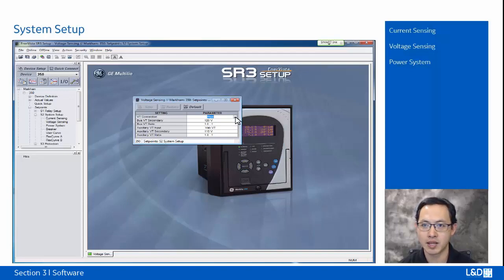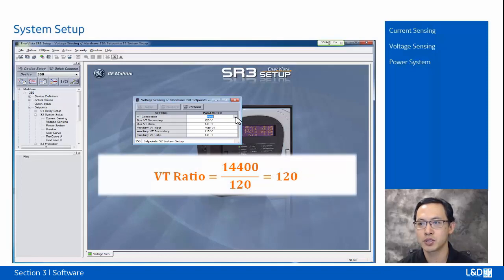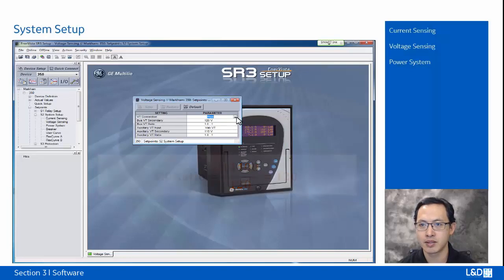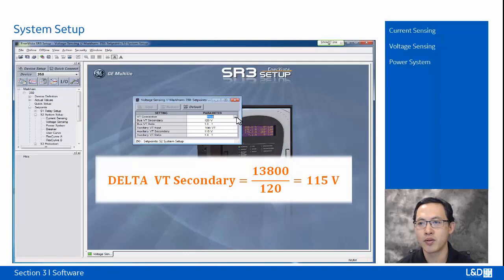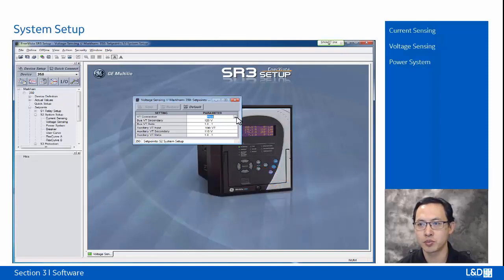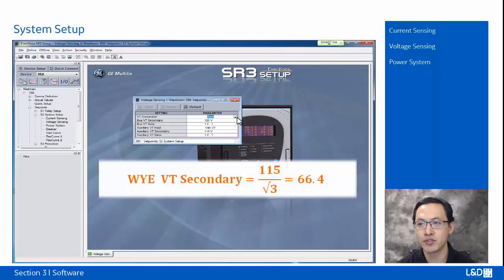And here is one example. On a source of 13.8 kilovolts line-to-line voltage with a VT ratio of 14,400 to 120 volts delta connection, then the secondary voltage to be entered is 115 volts. For Y connection, the voltage to be entered is 115 divided by root 3, that's 66 volts.